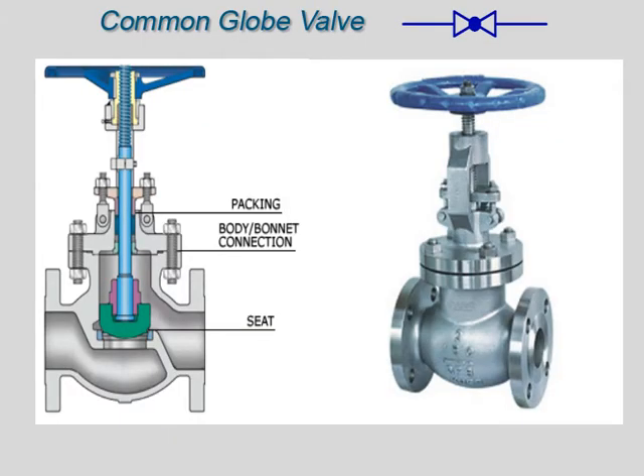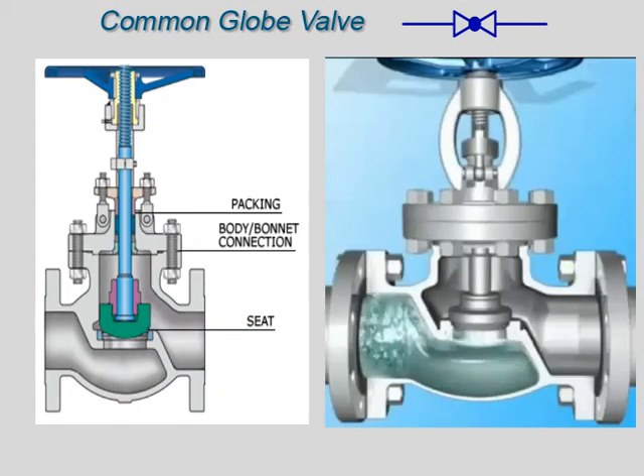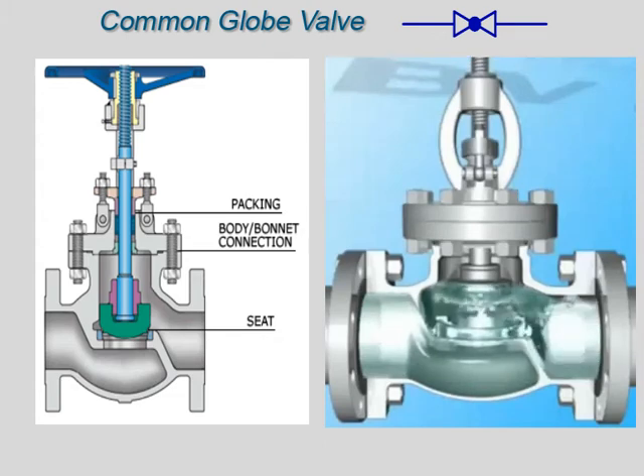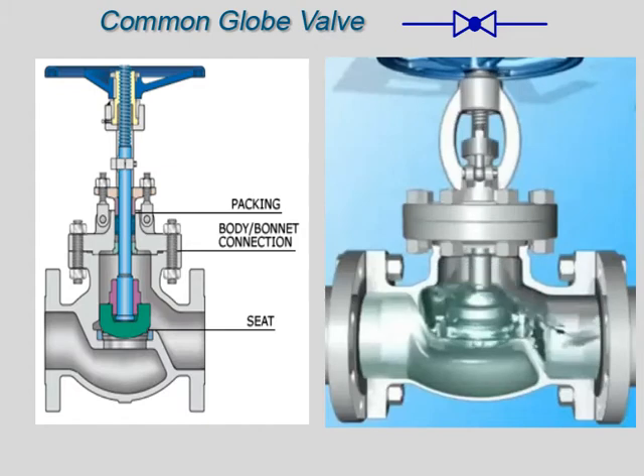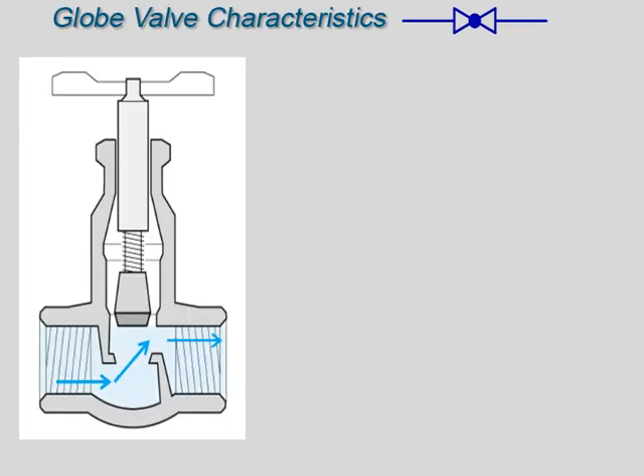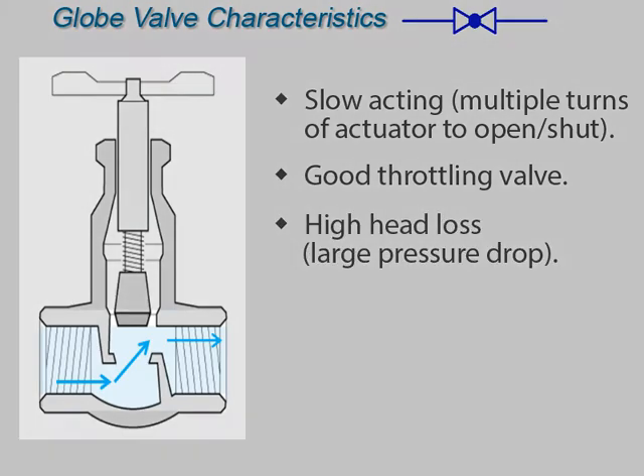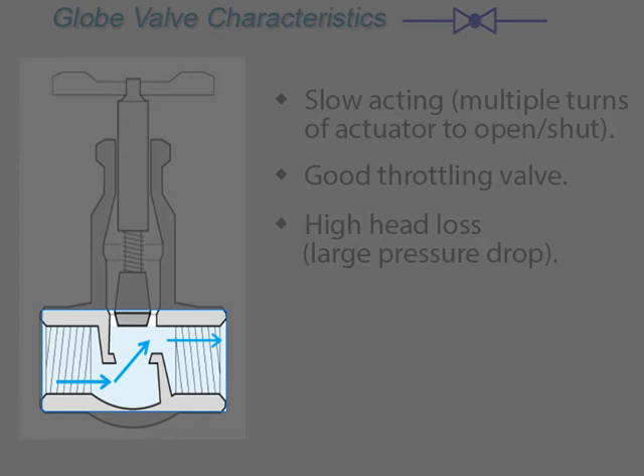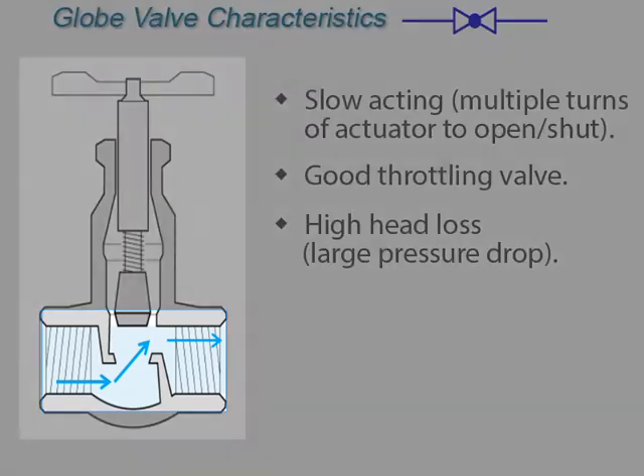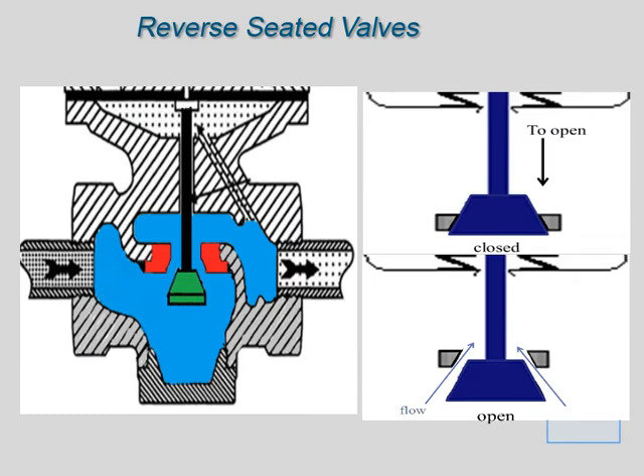Globe valves are the most widely used flow regulating valves. They are linear motion valves with excellent flow isolation and throttling characteristics. The essential principle of globe valve operation is the perpendicular movement of the disc away from the seat. The globe valve is slow-acting due to multiple turns of the actuator to fully open or shut the valve. The main advantage is good throttling characteristic. The disadvantage is the large amount of head loss that occurs across the valve due to flow direction changes and small openings in the seat. Globe valves can be designed so that the disc closes against or in the same direction of fluid flow. Valves that open in the direction of flow are normal seated or forward seated; valves that open against the flow are reverse seated. Manually operated valves are typically normal seated, while reverse seated valves are typically used with non-manual actuators for throttling purposes.